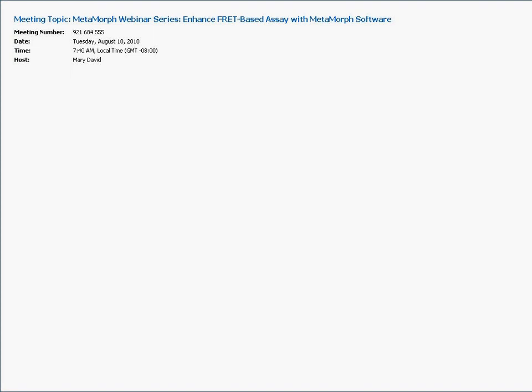Alfred Hernandez has a question: will MetaMorph capture the images for us, and where do we specify the order we want them to be acquired? Okay, MetaMorph can capture, and there's a variety of different ways of doing that. You can do simple acquire. In this case, you set up the wavelengths you want to do, whether it's CFP, YFP, and FRET is the illumination setting that you'll use.